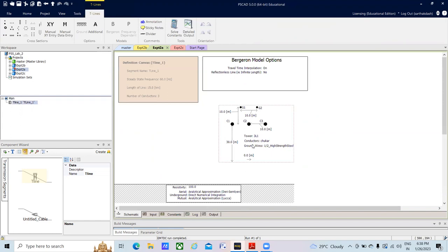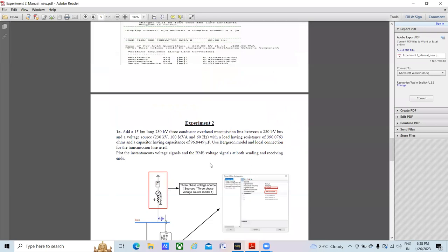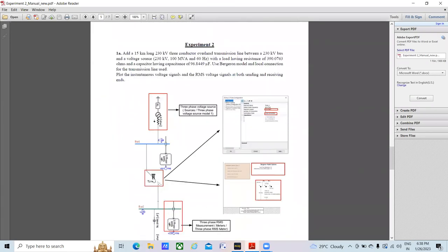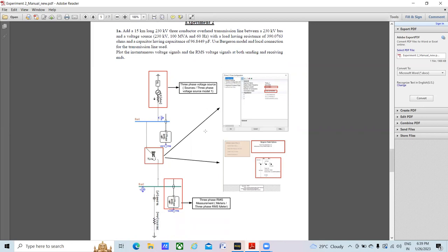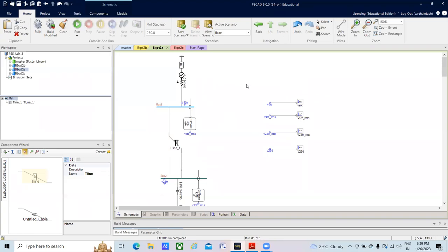I already have my Bergeron model and the three-conductor flat tower, so I am using those. As mentioned in the experiment, I just need a source operated at 230 kV, 100 MVA, 60 Hz — a three-phase source. The transmission line will use all the parameters we have already set.